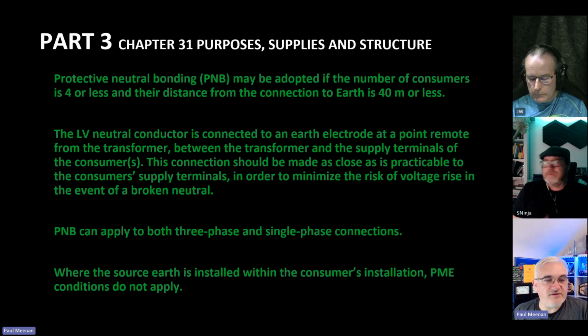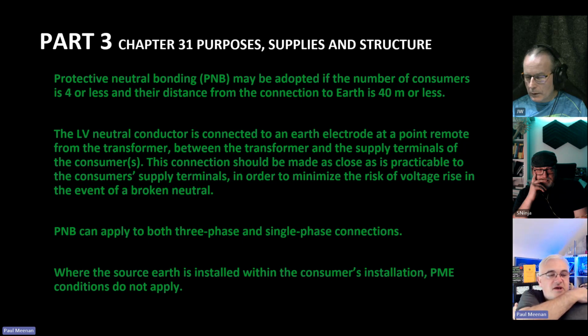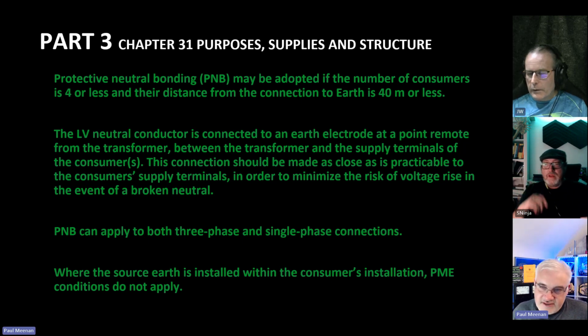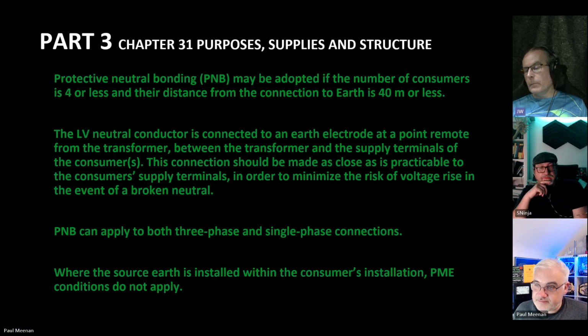The LV neutral conductor is connected to an earth electrode at a point remote from the transformer. Between the transformer and the supply terminals of the consumers, this connection should be made as close as is practical to the consumer supply terminals in order to minimize the risk of voltage rise in the event of a broken neutral. PNB can apply to both 3-phase and single-phase, and where the source earth is installed within the consumer's installation, PME conditions do not apply. So that's the actual guidance. I don't know where any of this has come from. I would like to understand more.